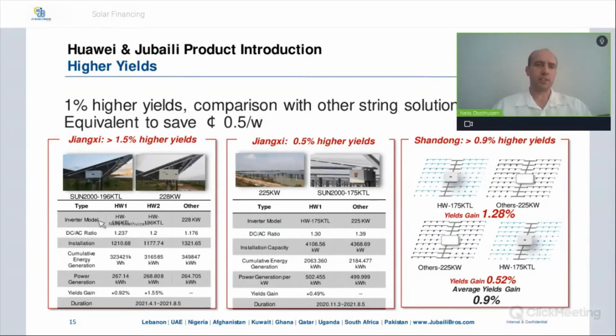In this first test case scenario, Huawei inverter was 196 kTL, and Huawei inverter 2 was also 196 kTL, but the third inverter brand was actually a larger 228 kilowatt. DC to AC ratios are specified, but in comparison with the third-party inverter, Huawei gave a 0.92% higher yield and also a plus 1.5% higher yield, over a duration of only 4 months.